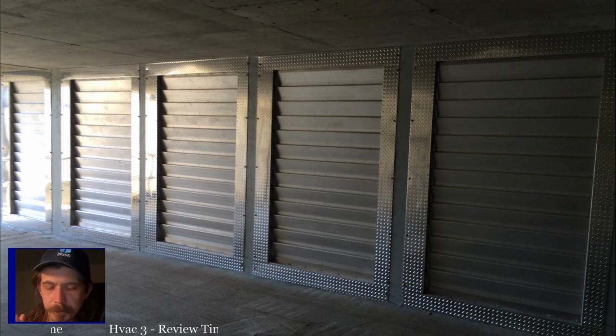So an ECM is basically going to have a motor control section on the motor. It's an electronically commutated motor. You're going to have a motor control that's going to essentially take the single phase power coming in, turn it into three phase, and send it to what's essentially a three phase motor section on the other side. So if you're troubleshooting the motor section of the ECM, it's exactly the same as troubleshooting a three phase motor.